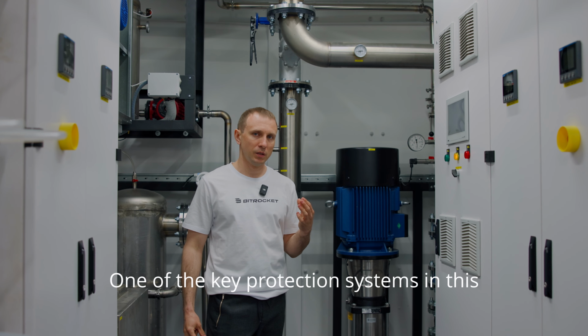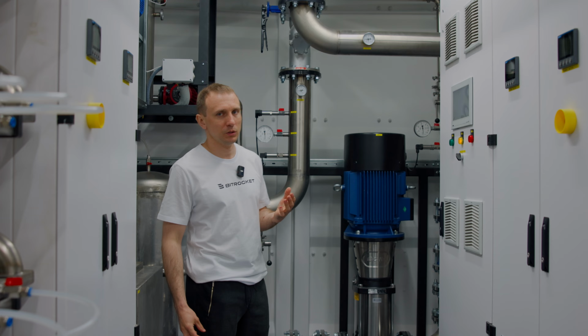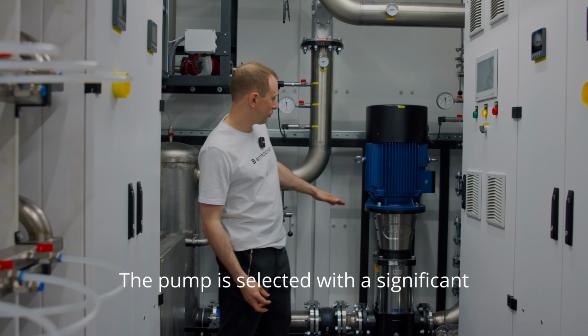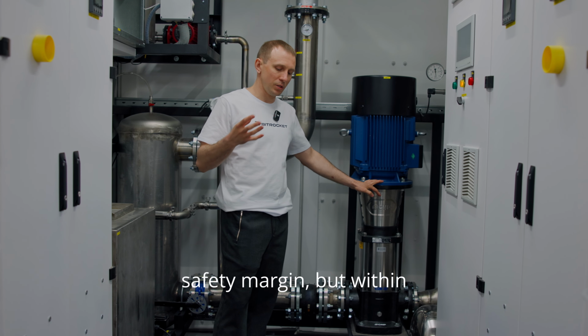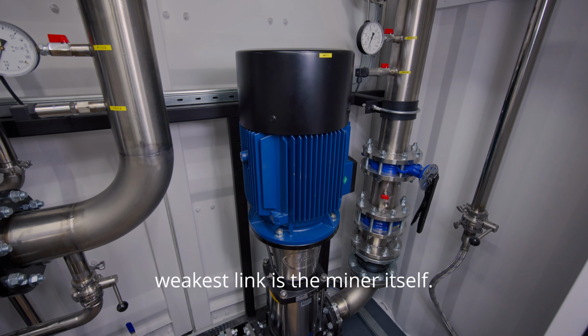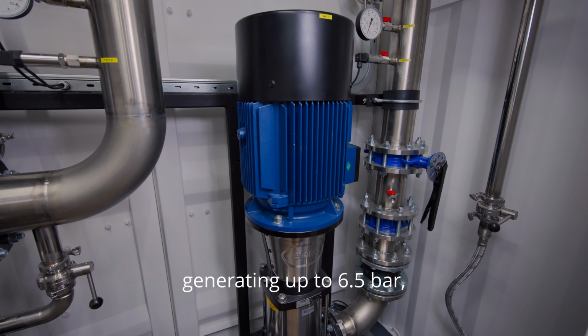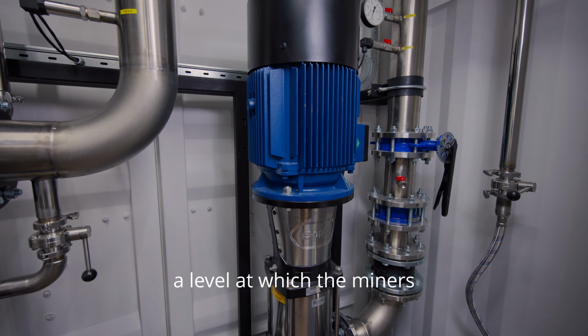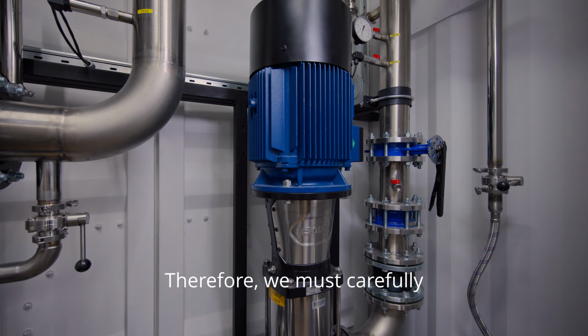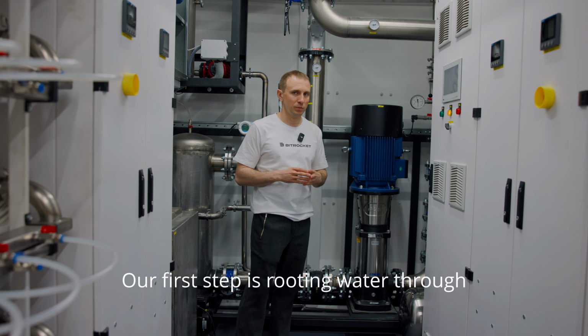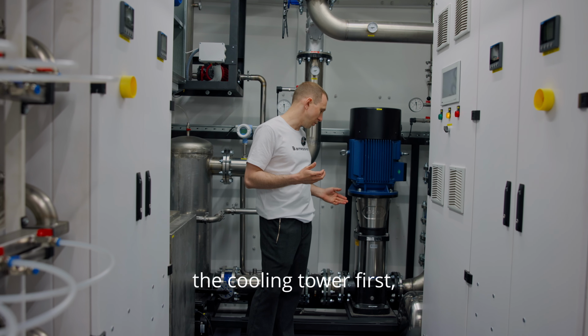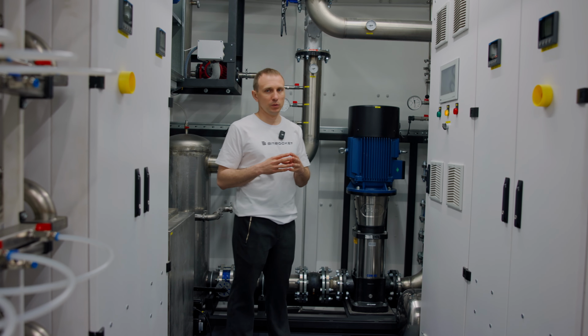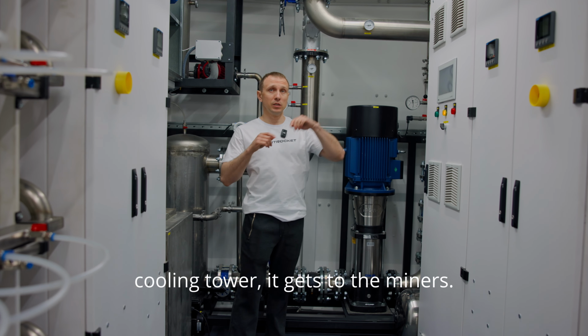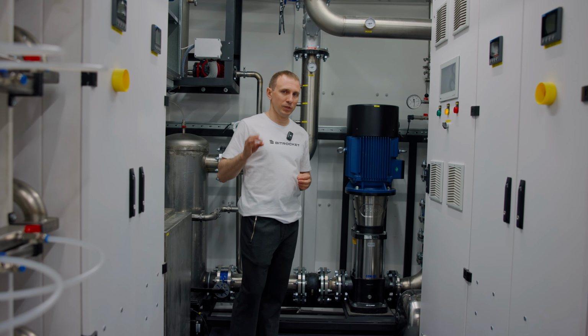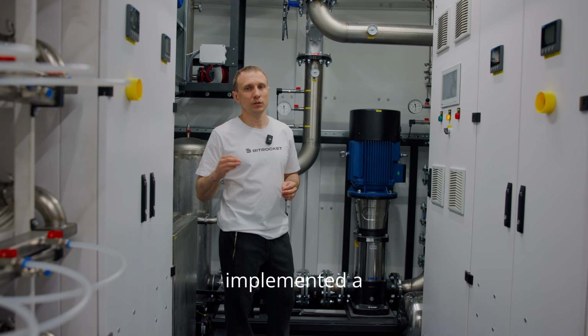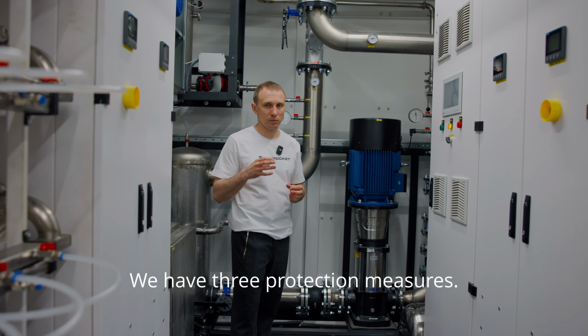One of the key protection systems in this container is overpressure protection. Here's the issue. The pump is selected with a significant safety margin, but within the hydraulic system, the weakest link is the miner itself. The pump is technically capable of generating up to 6.5 bar, a level at which the miners would simply rupture. Therefore, we must carefully monitor discharge pressure. Our first step is routing water through the cooling tower first, where we lose about 0.5 bar. But when the water returns from the cooling tower, it gets to the miners. In order to prevent overpressure, we've implemented a triplicated protection system. We have 3 protection measures.